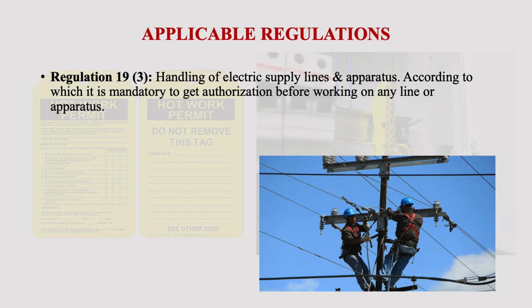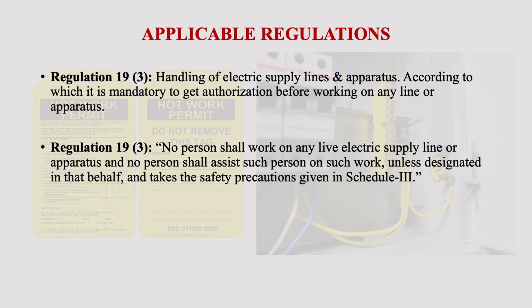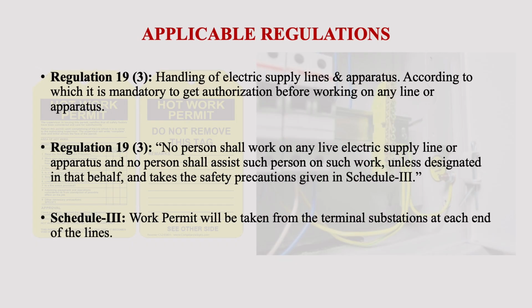Central Electricity Authority Regulations 2010, Regulation 19(3) also states that no person shall work on any live electricity supply line or apparatus and no person shall assist such person on such work unless he or she is designated in that behalf and takes the safety precautions given in Schedule 3. In continuation to the applicable regulations, we can see that Schedule 3 explicitly mentions what precautions need to be taken. One of the precautions to be observed pertaining to the work permit system under Schedule 3 is that the work permit will be taken from the terminal substations at each end of the lines.